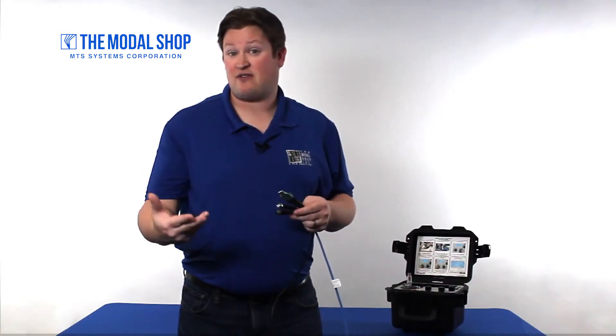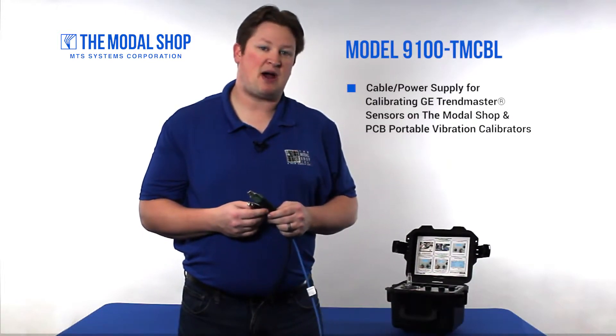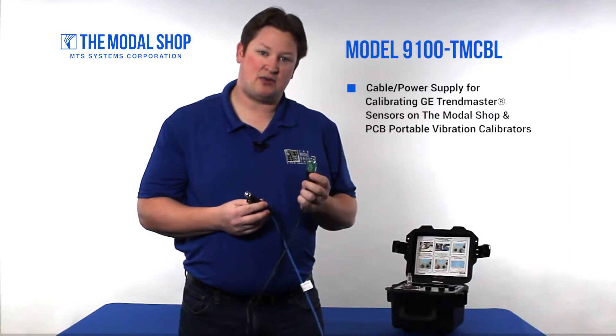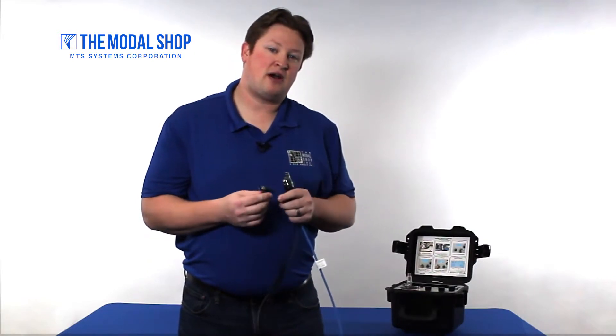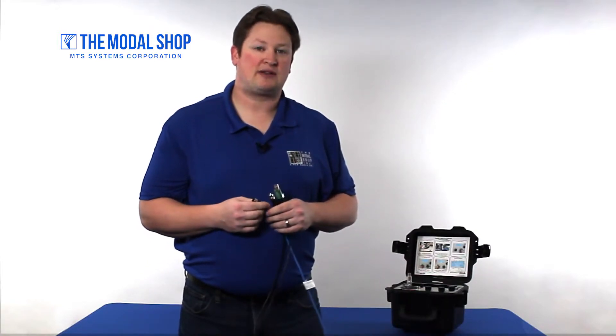This is about a 5 volt DC sensor, so we're going to use the USB power on top of the shaker to power it. For that, we've created a new model — model number 9100-TM-CBL. It's a cable and power supply that makes it very easy to test these transducers. There's no way to wire it up incorrectly. It has a USB connection, a BNC that goes to the test sensor input or your voltmeter, and the Bently Nevada 5-pin connector to connect to the sensor. This connector does have a keyway, so it can't be connected incorrectly. With this equipment, we can begin the test.